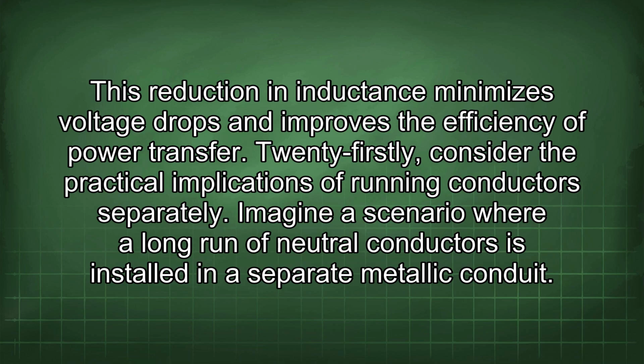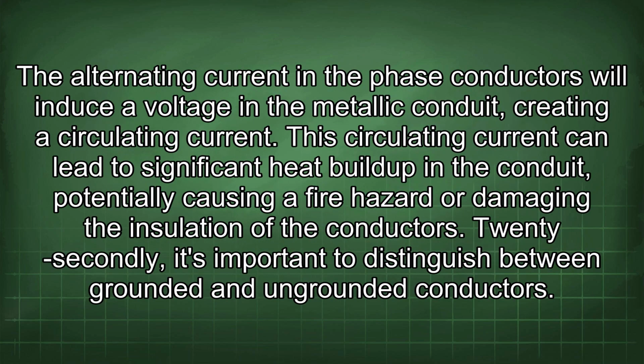21stly, consider the practical implications of running conductors separately. Imagine a scenario where a long run of neutral conductors is installed in a separate metallic conduit. The alternating current in the phase conductors will induce a voltage in the metallic conduit, creating a circulating current. This circulating current can lead to significant heat buildup in the conduit, potentially causing a fire hazard or damaging the insulation of the conductors.